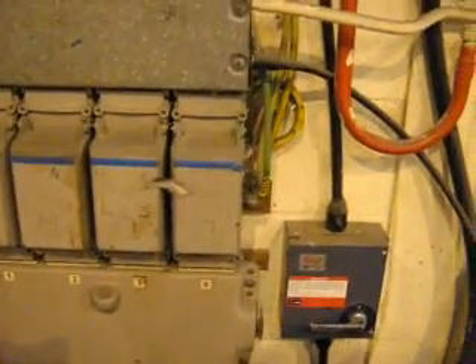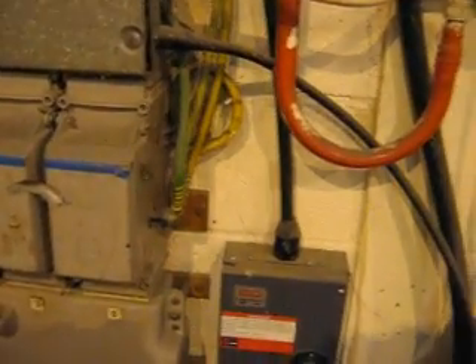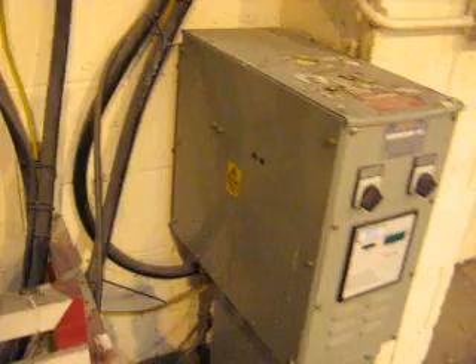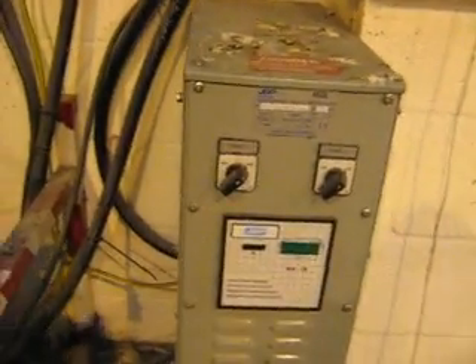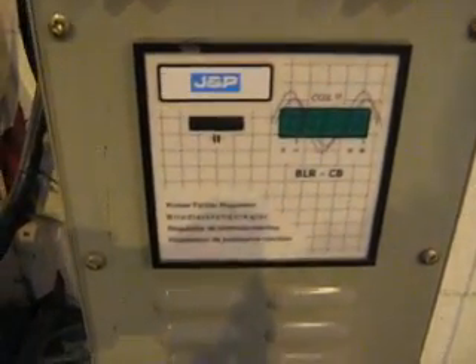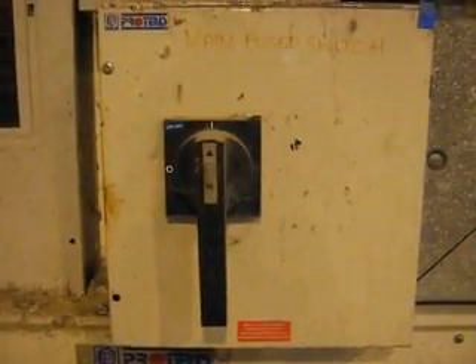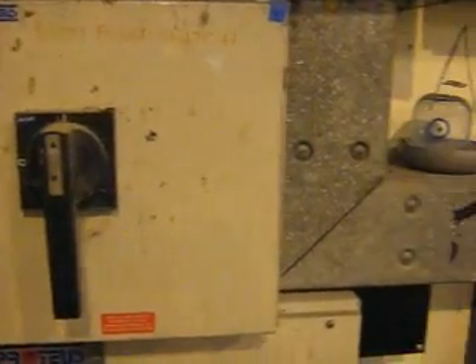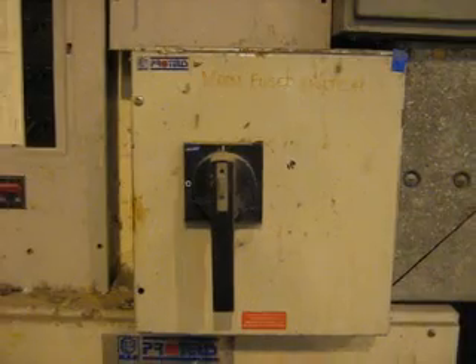This is a Crabtree C50 circuit breaker board, and this is the service, 400 amp TNCS. Just around the side here is the service earthing terminal. Just over to my right here is power factor correction equipment. At the moment it's switched off. I'm not quite sure why, but its equipment is rather crudely marked as the main fuse switch. Whether that is so or not, I'll have to determine by taking the trunking lid off. It's Proteus, which is bad news, and underneath is a busbar chamber, the main busbar chamber.